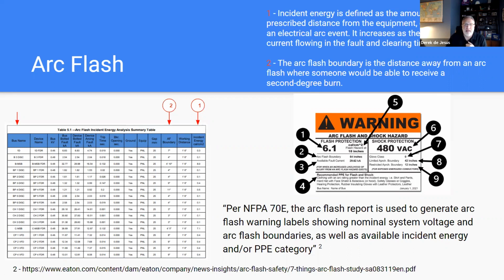The first I'm going to highlight is the incident energy available for that piece of equipment at that device. The second is the arc flash boundary. Arc flash boundary, what we're trying to determine there is the distance away from an arc flash where someone would be able to receive a 2nd degree burn. Now, this doesn't mean you need to stay 21 feet away or 31 feet away, but when you are working within that equipment or near that equipment and you wear that proper PPE, you are within that arc flash boundary.